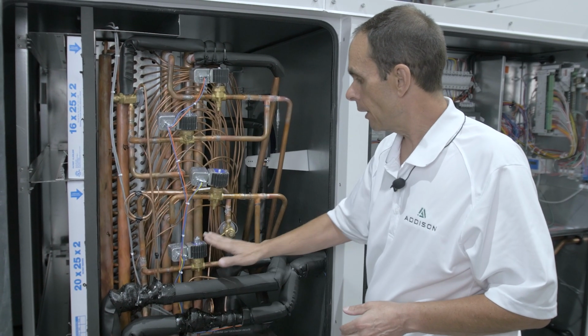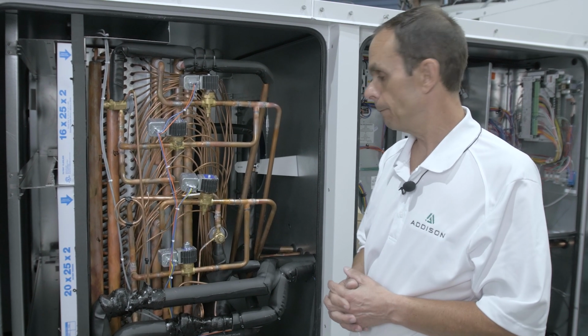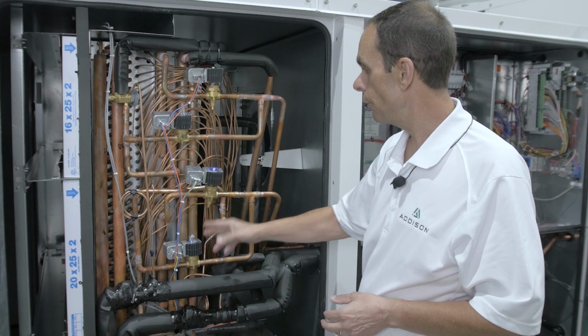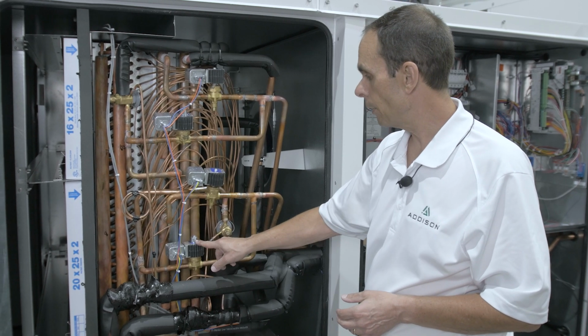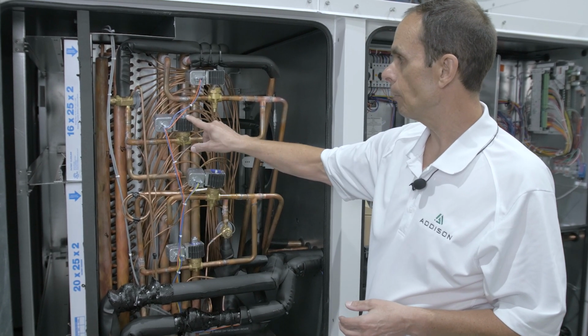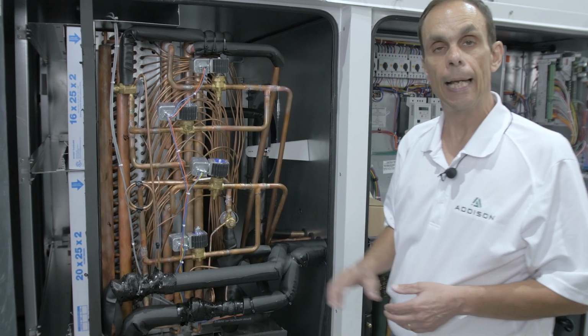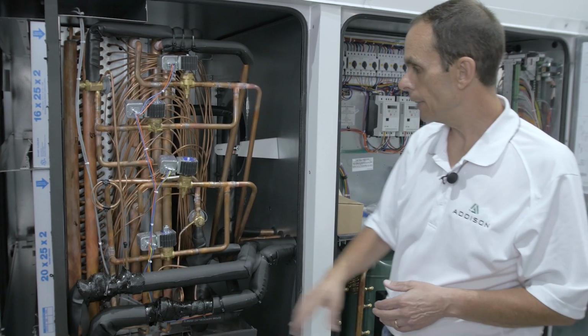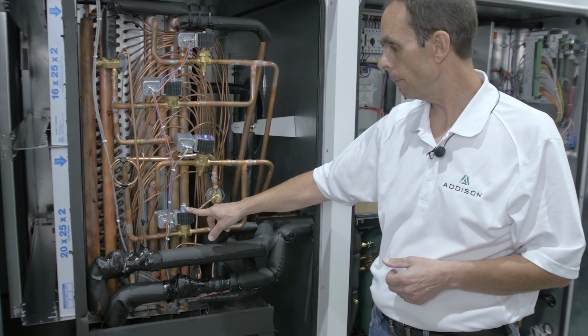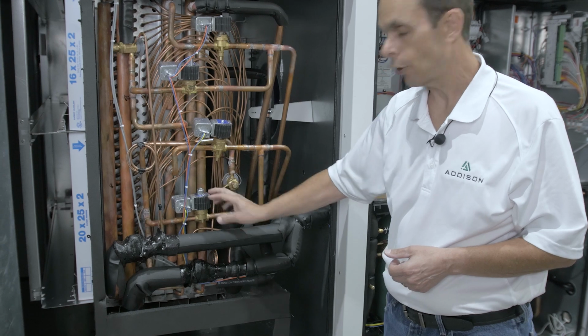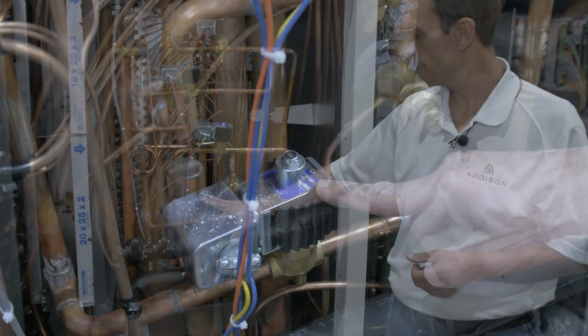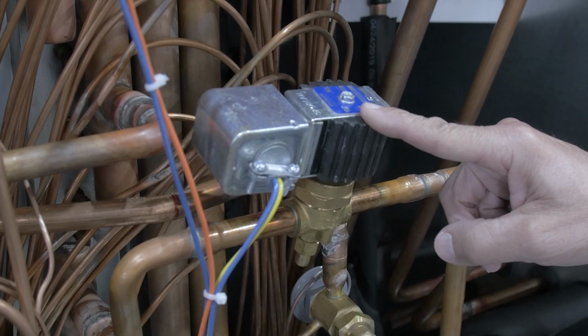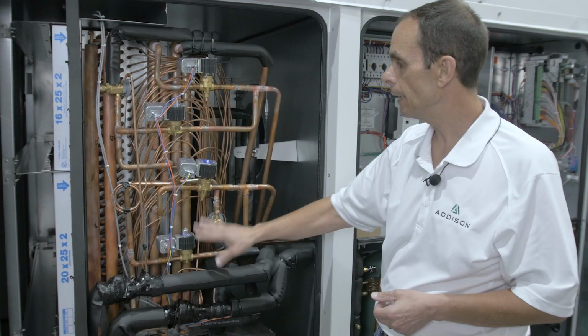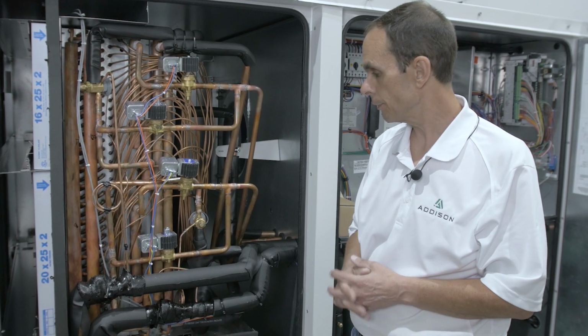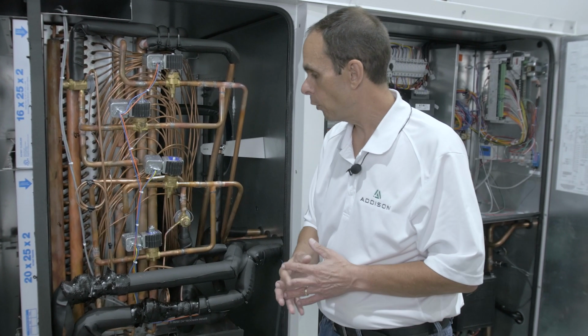These solenoids here are going to be for your switchable subcooling. We have two sets per circuit. You have a normally open, normally closed, normally open, and normally closed solenoid. And again, the way to identify those solenoids is by this little bushing on top of the coil. Basically, it's got a little bushing, so you can figure that as a normally open solenoid. Without the bushing, it's normally closed, and that's how you identify your switchable solenoid coils for your subcooling coil.